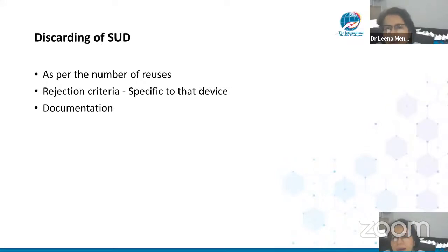Or maybe some part of it is damaged, the tip has broken. So one needs to frame all these rejection criteria, 1, 2, 3, very specific to the device that you are using as an SUD. And in case you're discarding according to any of these criteria, you need to document it again.